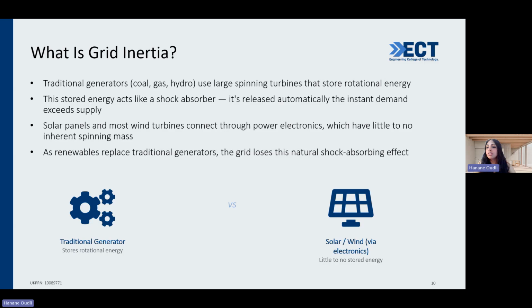It doesn't mean inverter-based resources cannot support frequency—they absolutely can. But it means the response has to be provided through a control system rather than relying automatically on the same physical response. So when we talk about inverter-based resources, the control system becomes very critical because of the low inertia compared to what synchronous machines have.